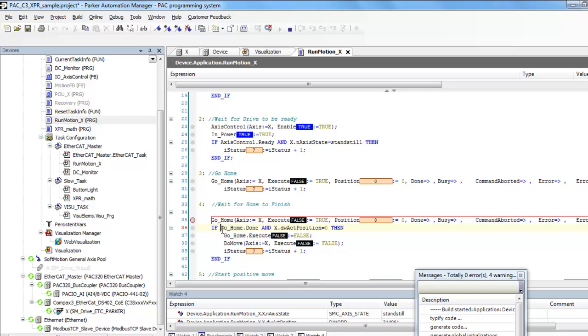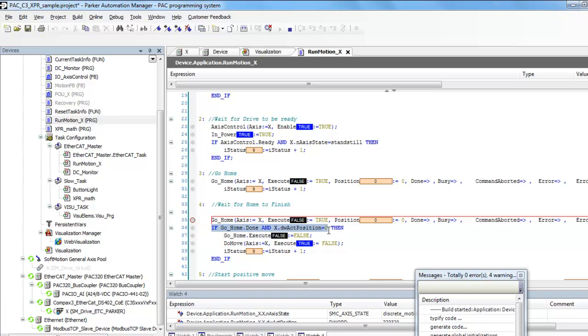As long as that's successful, that sets the position to zero. All the homing is actually done at the drive, so in this case the Compax 3, all the limit sensors and the home sensor are actually done at the Compax 3.